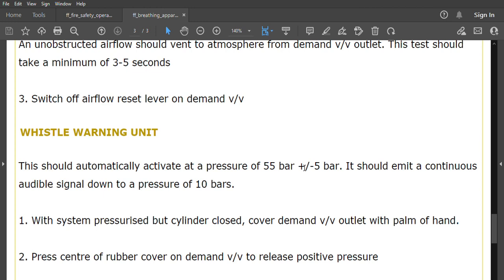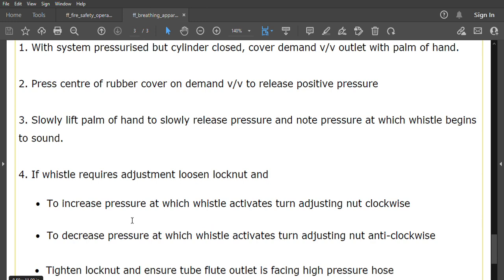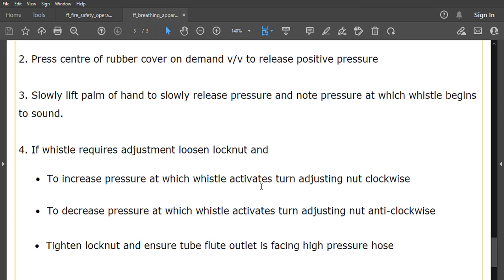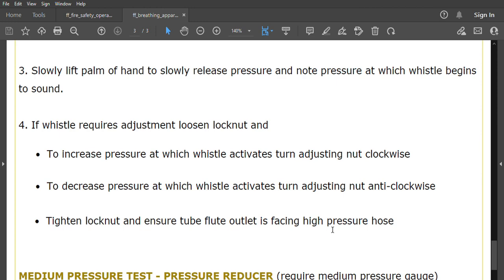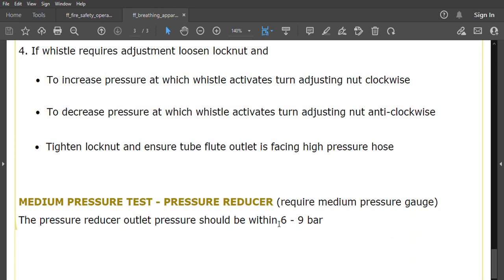The whistle warning unit should automatically activate at a pressure of 55 bar plus or minus 5 bar, emitting a continuous audible signal down to 10 bar. To test: pressurize the system with the cylinder closed, cover the demand valve outlet with your palm, press the center of the rubber cover to release positive pressure, then slowly lift the palm and note the pressure at which the whistle begins to sound. To adjust: loosen the lock nut and turn the adjusting nut clockwise to increase the activation pressure, or anti-clockwise to decrease it. Tighten the lock nut and ensure the tube flute outlet faces the high pressure hose. The medium pressure test (pressure reducer) requires a medium pressure gauge — the outlet pressure should be within 6 to 9 bar.